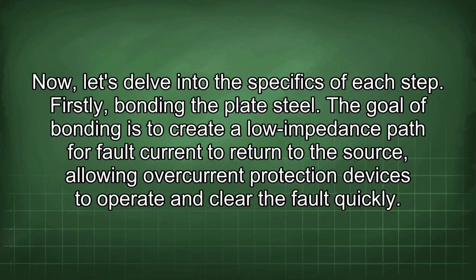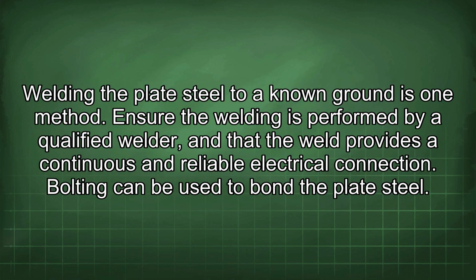Now let's delve into the specifics of each step. Firstly, bonding the plate steel. The goal of bonding is to create a low impedance path for fault current to return to the source, allowing overcurrent protection devices to operate and clear the fault quickly. Welding the plate steel to a known ground is one method. Ensure the welding is performed by a qualified welder and that the weld provides a continuous and reliable electrical connection.